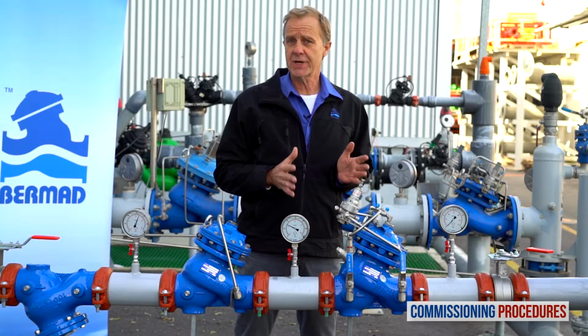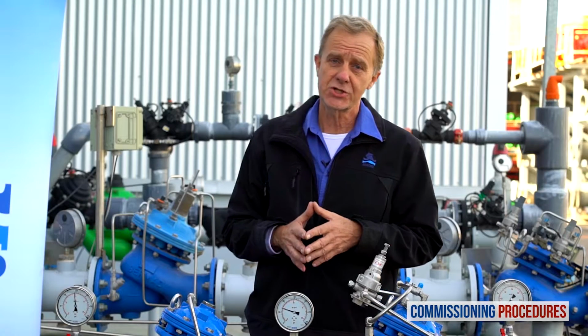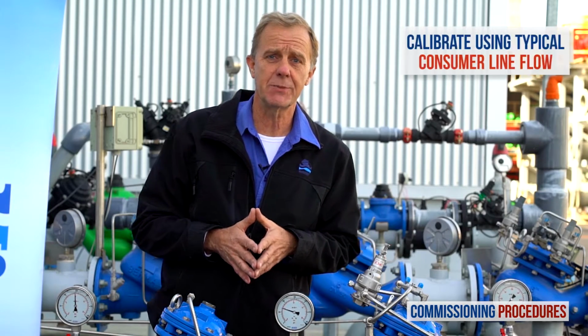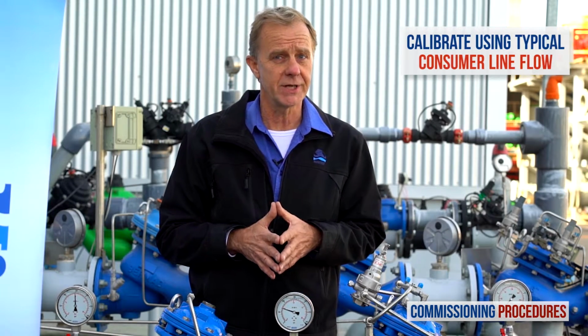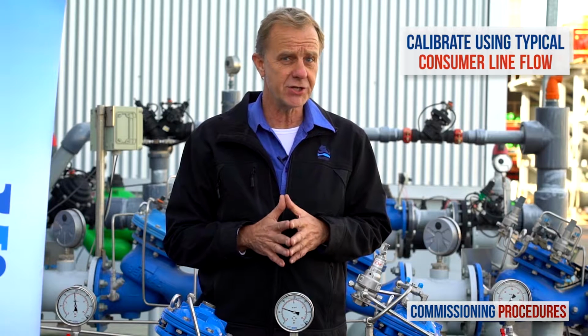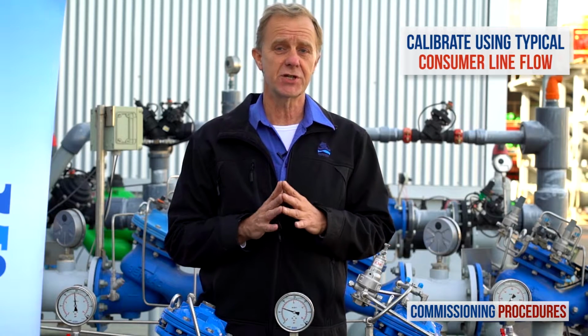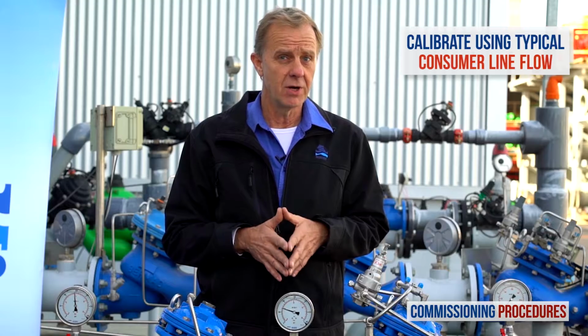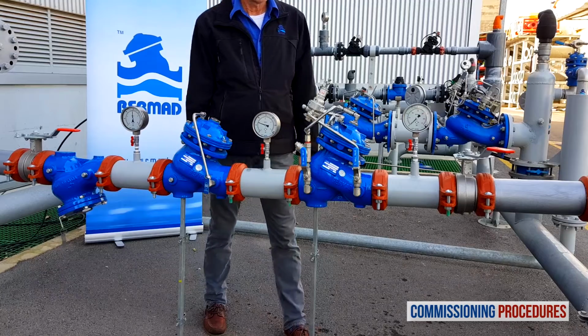Note that the calibration cannot be done without flow. To simulate actual conditions, you should have a typical consumer line open while calibrating, which should give you an average system flow rate. If this is not achievable, then a minimum flow will suffice, though not ideal.